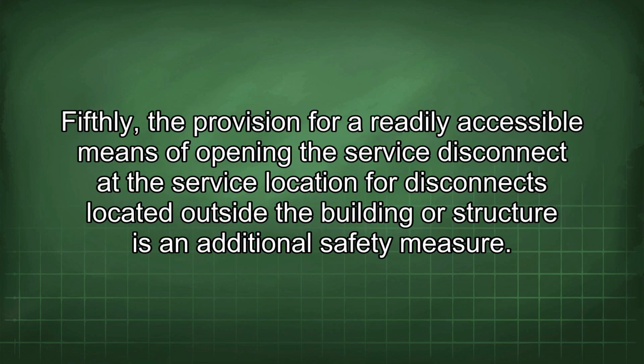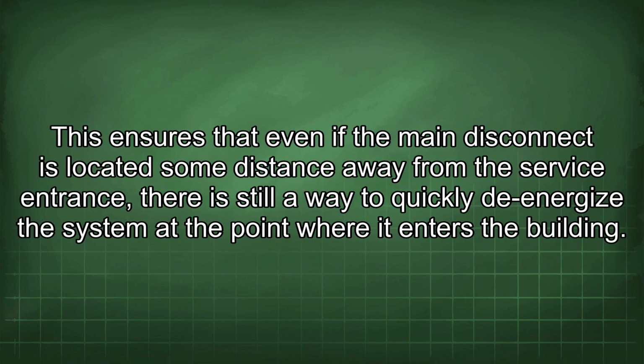Fifthly, the provision for a readily accessible means of opening the service disconnect at the service location for disconnects located outside the building or structure is an additional safety measure. This ensures that even if the main disconnect is located some distance away from the service entrance, there is still a way to quickly de-energize the system at the point where it enters the building.